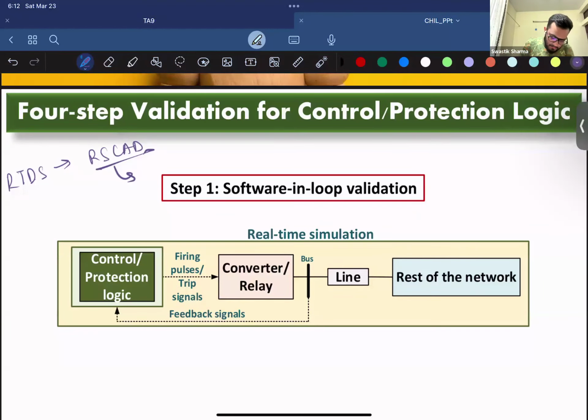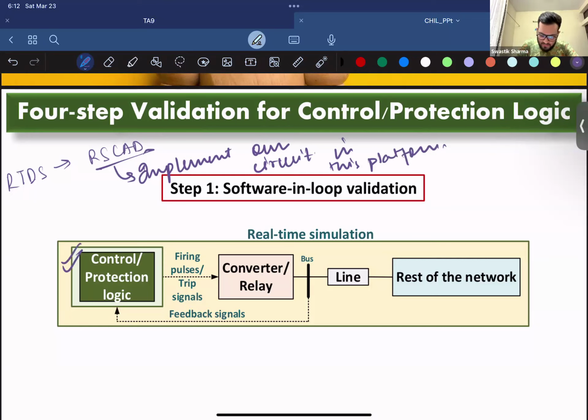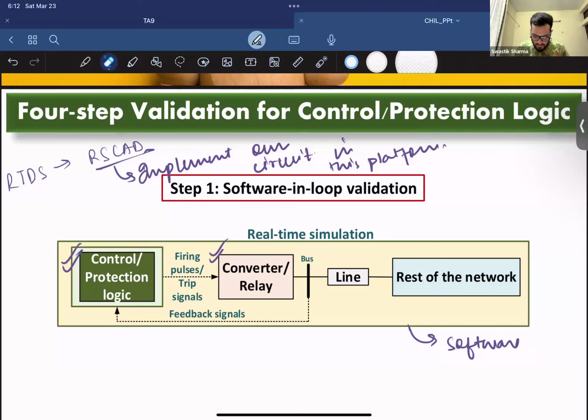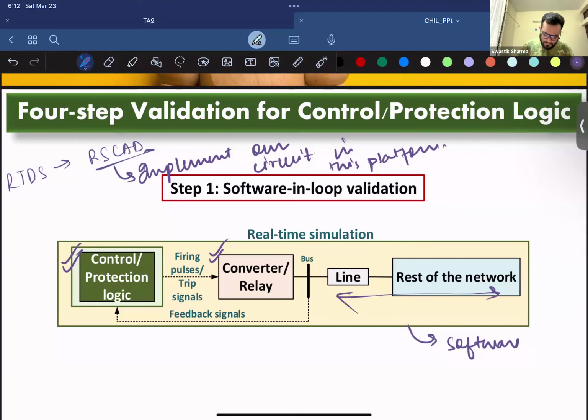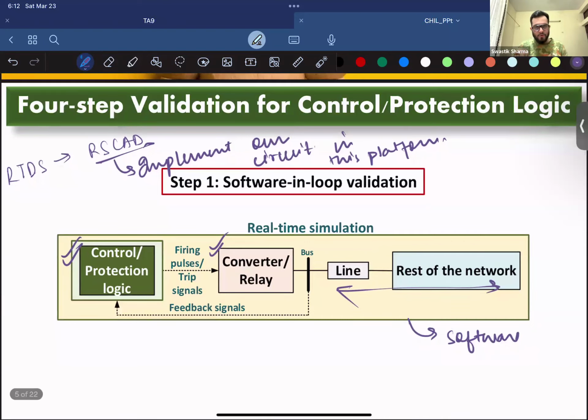We first implement our circuit on this platform. All of our control or protection logic is entirely in software—our controller, protection logic, converter or relay. Control means firing pulses for converters and trip signals for relays. I'm showing this for both protection and control of converters, connected to the rest of the network at a bus on the line. This is software in loop validation.